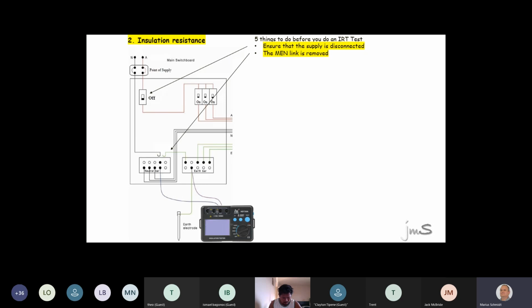Now guys, earth and neutral, if your link was in, it will give you a fault. Make sense? Next thing, you must always remember to disconnect your main neutral. Because if you don't, you're going to get a short between neutral and earth via the star point of the transformer. Try that one day. Test between earth and neutral. You get a short. When you disconnect the main neutral, the fault will go away. So what you're doing is testing between earth and neutral to your neighbor, to the other neighbor, to the transformer. Have a look. You guys will pick it up. Some of you will wonder, oh, is that why I always got a short?